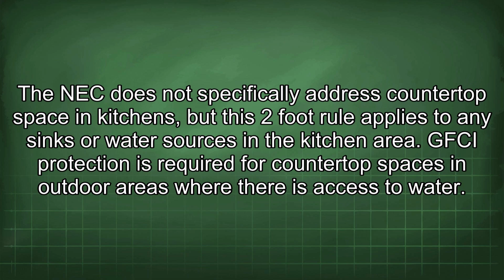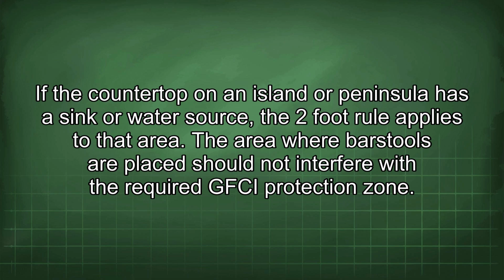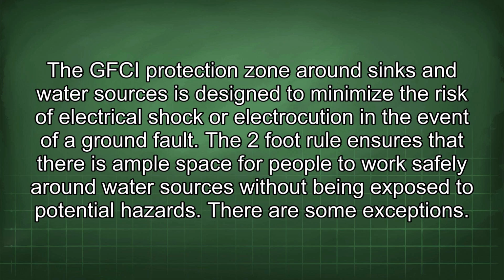GFCI protection is required for countertop spaces in outdoor areas where there is access to water. If the countertop on an island or peninsula has a sink or water source, the 2-foot rule applies to that area. The area where bar stools are placed should not interfere with the required GFCI protection zone. The GFCI protection zone around sinks and water sources is designed to minimize the risk of electrical shock or electrocution in the event of a ground fault.